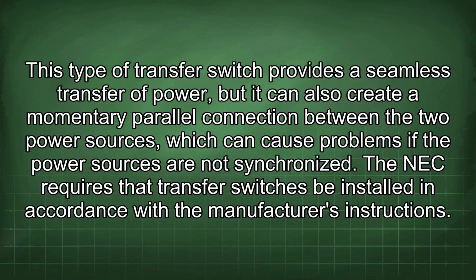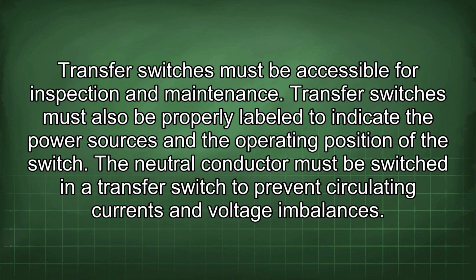This type of transfer switch provides a seamless transfer of power, but it can also create a momentary parallel connection between the two power sources, which can cause problems if the power sources are not synchronized. The NEC requires that transfer switches be installed in accordance with the manufacturer's instructions. Transfer switches must be accessible for inspection and maintenance. Transfer switches must also be properly labeled to indicate the power sources and the operating position of the switch.